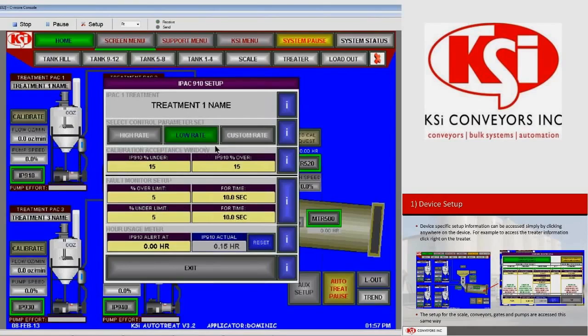The purpose of these is mainly to keep you from making a mistake when calibrating your pump, from entering an additional 0 or an additional number. We don't want you to be off a dramatic amount when it is not right. You can increase this acceptance window if you want. If you know that you really are calibrating and whatever the treatment you're using really is 20% off, you can change these amounts.